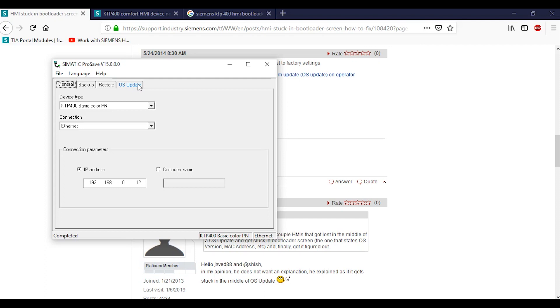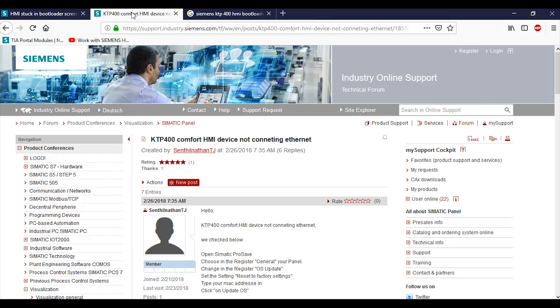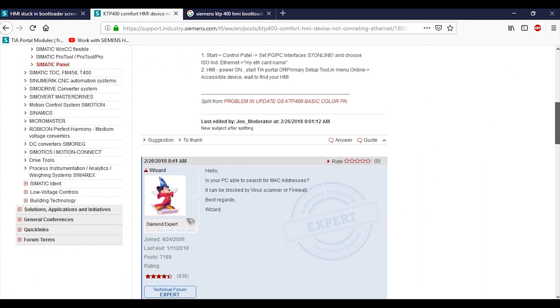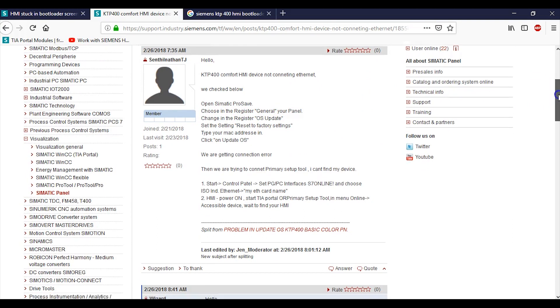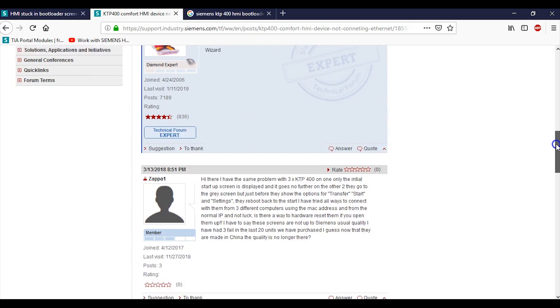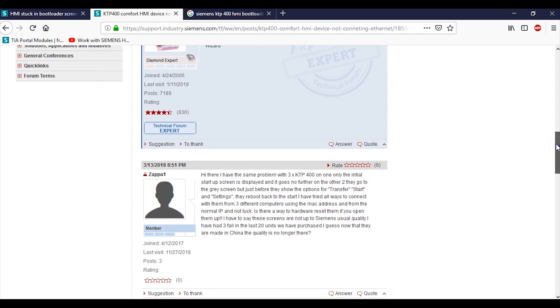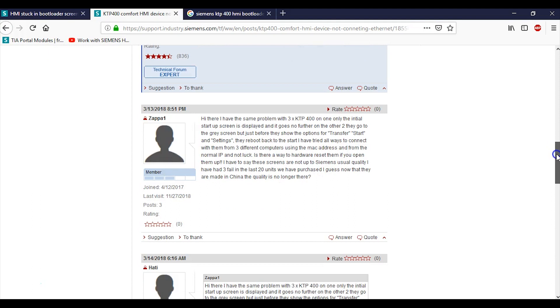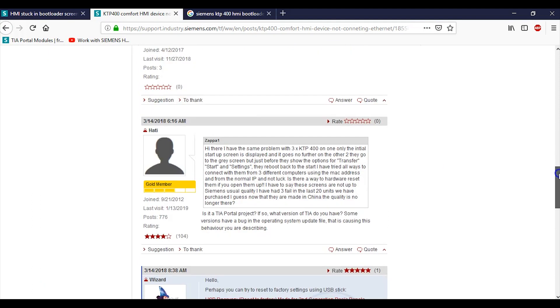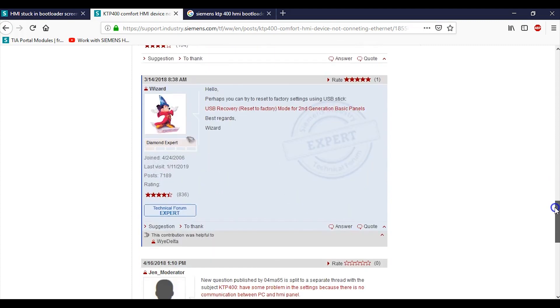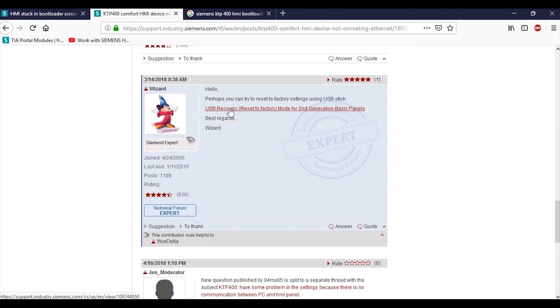After a little bit more hunting, I found that this guy - KTP comfort HMI device not connecting to the ethernet - kind of the same thing as what I was looking for. When I scroll down to the bottom, again they were mentioning to open that Simatic ProSave and try and have it talk to it. But I can't have my laptop talk to my HMI, so I need another way to do it. I remember that there was a USB port on the bottom of the HMI. Then all of a sudden it says here from the wizard: Hello, perhaps you can try to reset to factory settings using the USB stick. Oh, that sounds good!